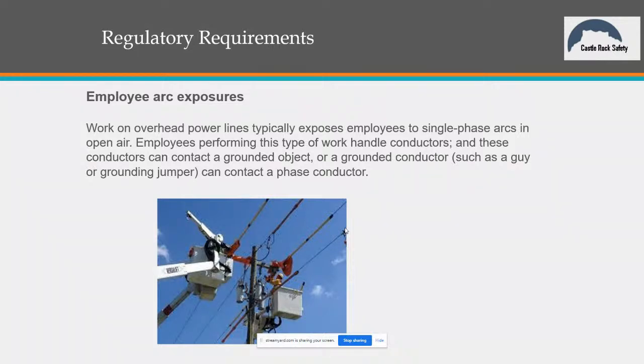When you're working on overhead lines, it's typically going to expose you to a single phase arc in open air. Now, if you remember, IEEE 1584, what are the voltage ranges for that? 208 up to 15 kV. Right, and it's also only for 3-phase. The 1584 equations consider everything a 3-phase event. So if I use 1584 to calculate the incident energy on an overhead line, the number that I come up with is going to be extremely conservative. It's going to be way beyond what my actual exposure would typically be.